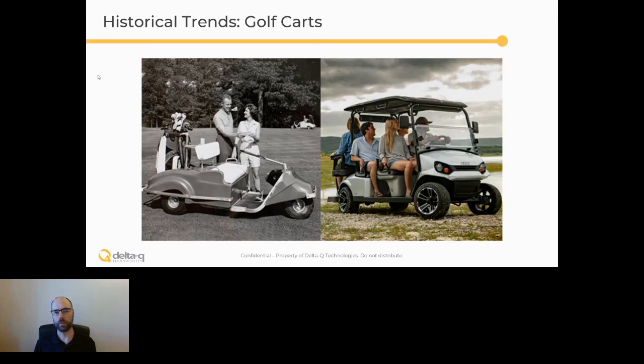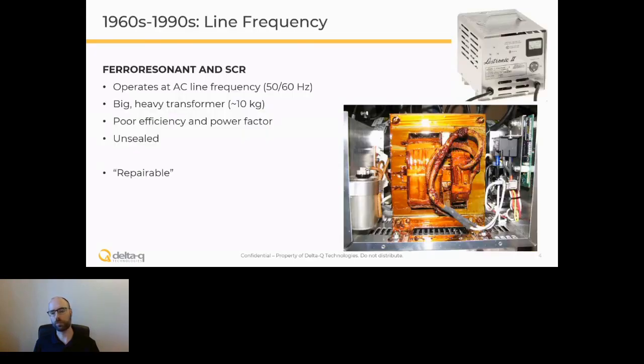Chargers operated at the AC line frequency of 50 or 60 hertz. They were typically ferroresonant or SCR based—silicon controlled rectifier. But the main feature is what you see in the middle of that open charger: inside that bent sheet metal box, the charger is largely a big, heavy transformer. Because it's operating at 60 hertz, it ends up being at least 10 kilograms of steel and copper, which is a major size and weight penalty, with fairly poor efficiency and poor power factor.